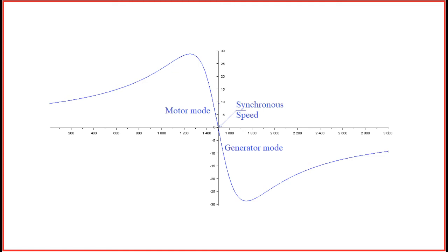Now if motor is driven by some prime mover above the synchronous speed, then as the mechanical power is given, motoring torque supplied by low frequency rotor currents will be replaced by prime mover's torque. Under this condition, magnetizing current required to produce and rotate synchronous speed shall be supplied by grid as before.